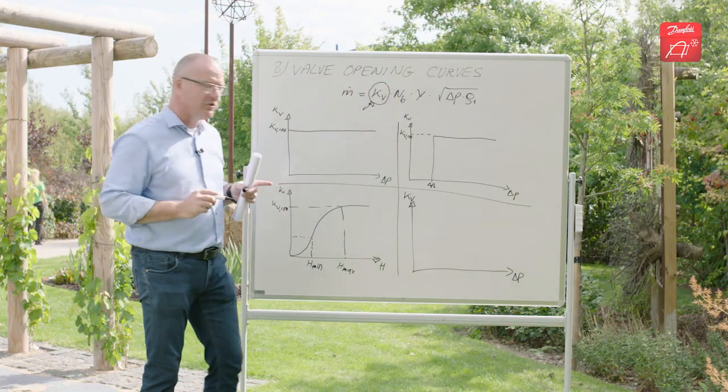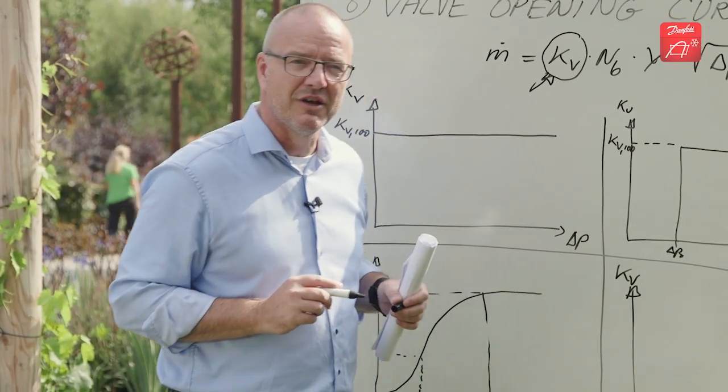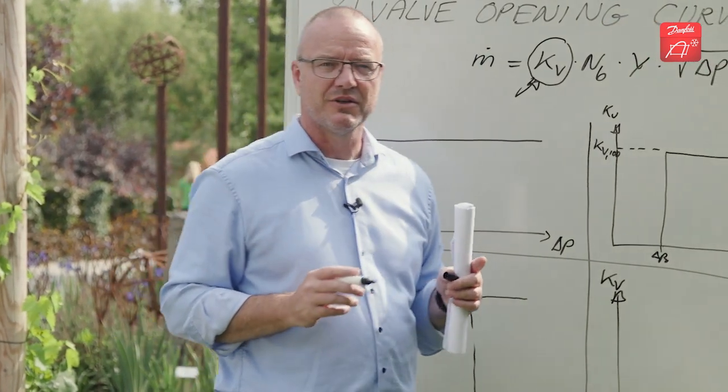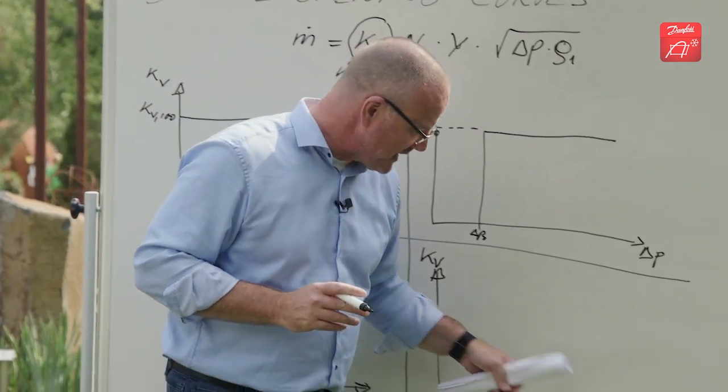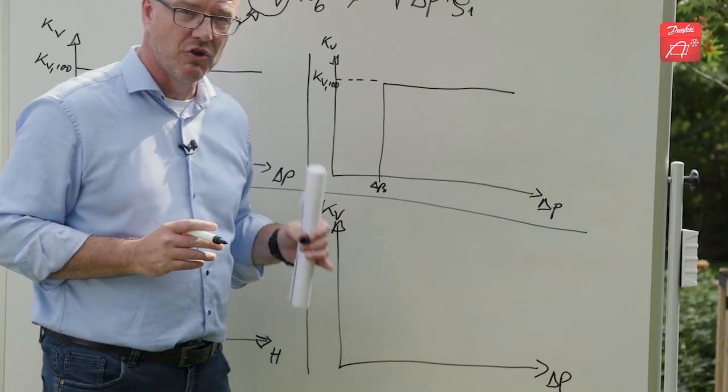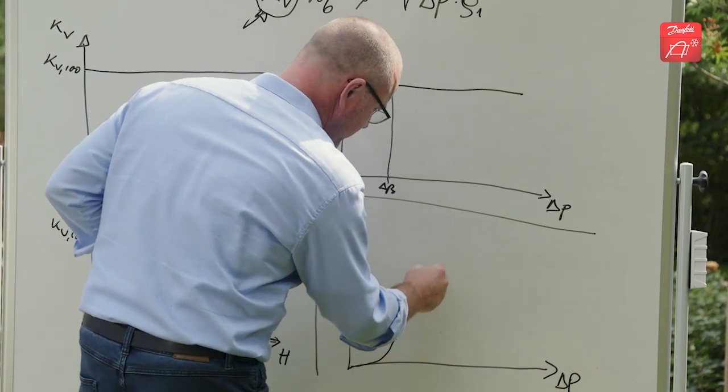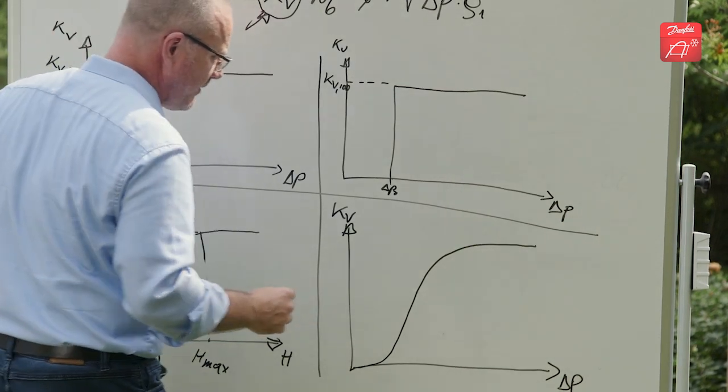The final valve type we look at, that is the servo piston operated solenoid or control valve. These valves actually require a certain pressure drop to open at all. And they require sometimes quite a bit of pressure drop to open fully. The characteristic of these valves looks very much like the characteristic of the direct operated valves.